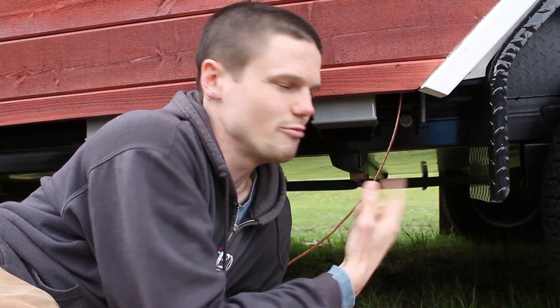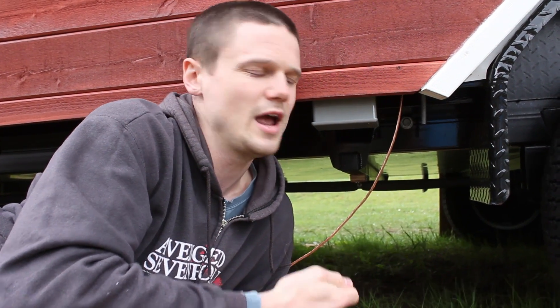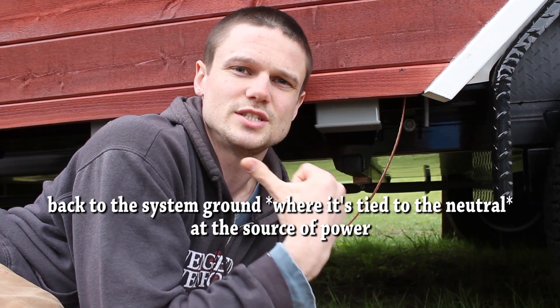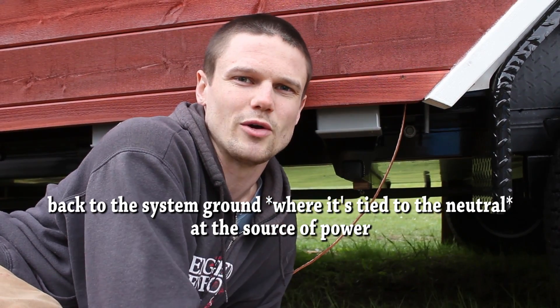Obviously there's a lot of metal under here and in the event of some kind of electrical mishap or damage to a wire and a live wire touches any of this metal, we want to make sure that there's a path through the bond back to the system ground at the source of power.